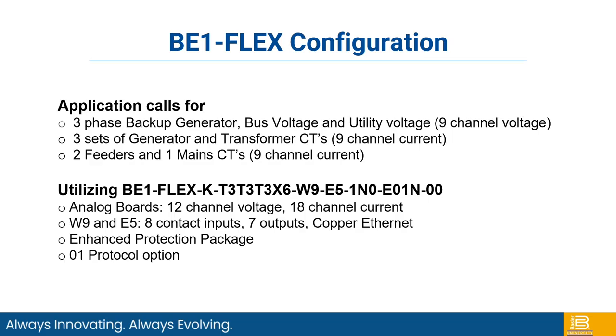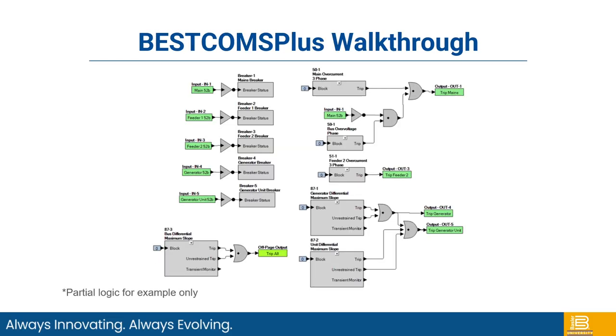So the application calls for a 3-phase backup generator, bus voltage and utility voltage. So 9-channel voltage being used. 3 sets of generator and transformer CTs. So that's 9 current inputs. 2 feeders and 1 main CT there. You have the analog boards utilizing the 12-channel voltage, the 18-channel current, the W9 with the 8 outputs and the 7 outputs and the 8 inputs, along with the copper Ethernet and the enhanced protection and protocol package.